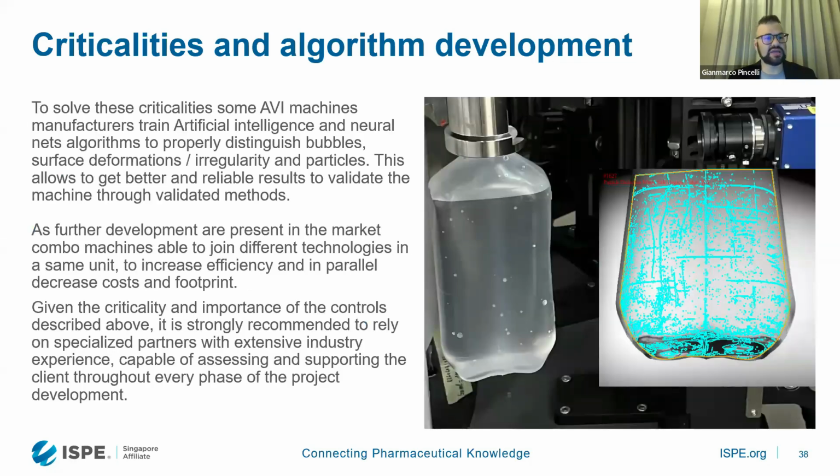Okay, move ahead. As well, for a product like that, a blow-fill seal bottle, the bubbles are stuck on the walls as well. Here, the algorithm can detect this bubble as a bubble and does not treat it as a cosmetic defect. A normal system identifies this bubble as a reject. A system based on AI can learn about the bubble position and bubble characteristics, and can avoid making false rejections for that.